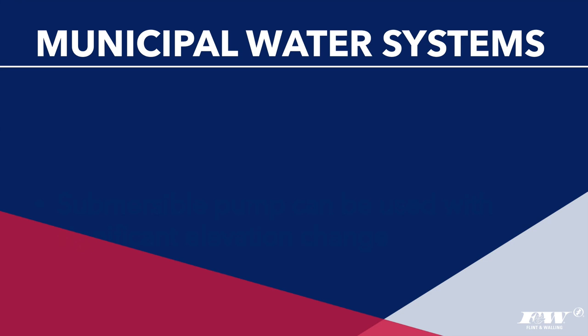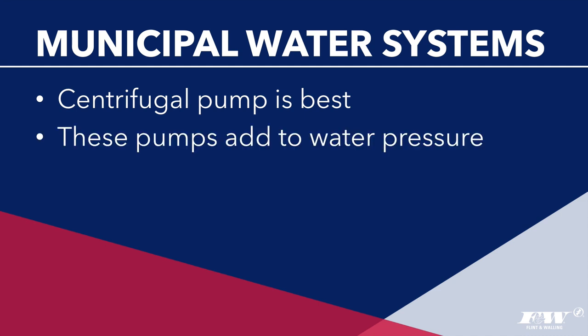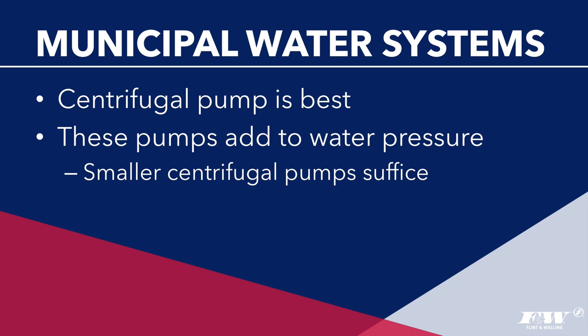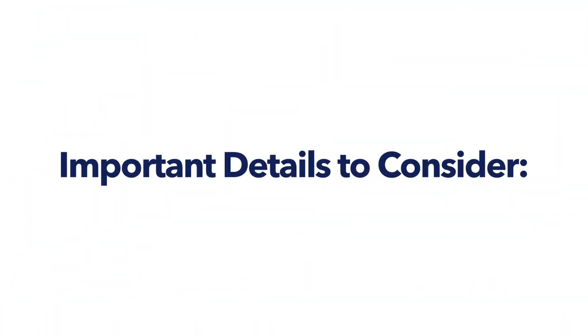If your irrigation system is connected to a municipal water system, the best pump is a centrifugal booster pump. Because the incoming water is already pressurized, these pumps only add to the existing pressure, so a smaller pump is sufficient. Most manufacturers carry a line of booster pumps for this purpose. Importantly, a booster pump cannot change the amount of flow available — that is determined by the size of the water meter. A booster pump can only boost the pressure of the system.